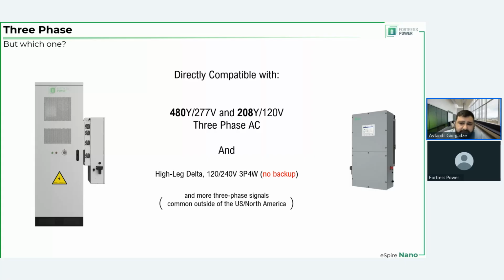There are three models of this inverter. One of them also can do high-leg delta, so that will be a three-phase four-wire delta configured system. But it can only do it in grid-tied mode, just importing, exporting, doing self-consumption, but no backup whatsoever. Those are the three-phase signals that we want to focus on, but obviously it can do much more. It's just that these are the most relevant ones in North America, and even more specifically the US and Canada maybe. I'm not too familiar with Mexico's grid regulation, but I was assured that the grid AC signal types that are common in Mexico, this inverter can easily cover.